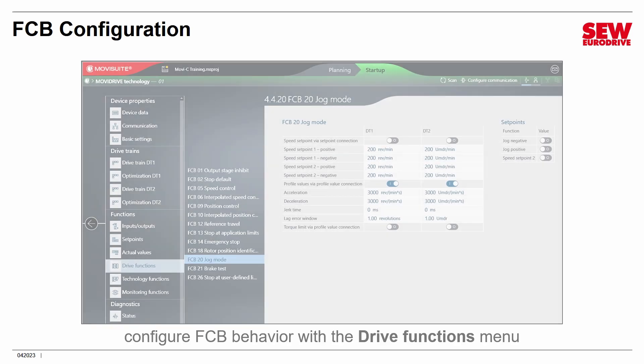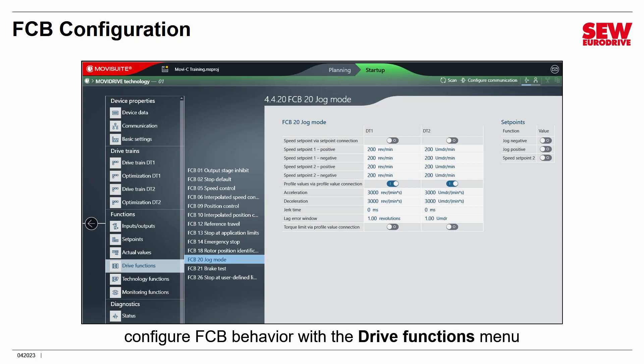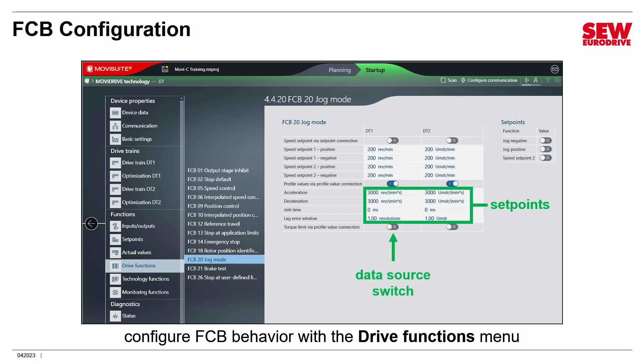FCBs can be configured. The way you do this is go to the Drive Functions menu, and you'll get a list of the available FCBs. Pick one as a submenu, and you'll see a screen with parameters and switches that configure its behavior. The one shown here is for jog mode, which is a very common one we'll be playing with in the next lab. For example, there are setpoints, jog acceleration and deceleration values that can be changed, and switches you turn on and off to control where data is coming from. I encourage you to explore this menu and submenus to get an idea of what's out there.